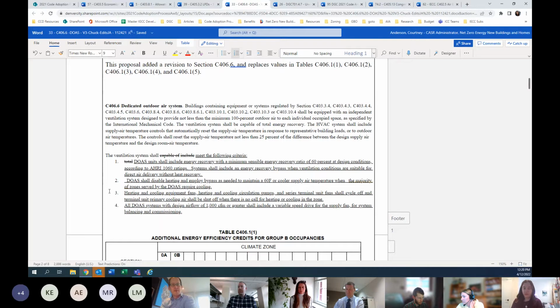The second, DOAS shall disable heating and employ bypass as needed to maintain a 60-degree or cooler supply air temperature when the majority of zones served by DOAS require cooling. So some DOAS systems might just serve one space or be dumping air into a common space, but others may be serving multiple systems. So we want to make sure that the DOAS isn't creating any unnecessary heating load by pushing air that's too cold for the space that might increase the heating load on the building.